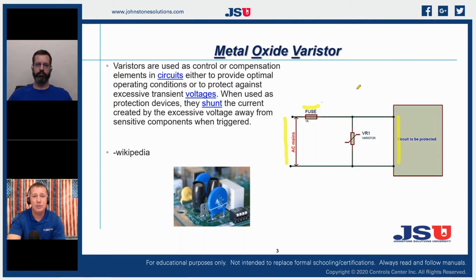And it doesn't use its resistance under normal operating conditions. What happens is when it sees a high amount of voltage, it generates heat and changes the resistance of the varistor so that it can redirect the current. So all it's doing is creating a new path of least resistance back to neutral or back to ground, depending on how the circuit is wired. Actually looking at this one, that says AC. That would have been a 120 system, so it would have had a hot and a neutral. So it was bringing it from hot to neutral, and it's going to land it back on neutral, or it's going to land it back on ground. If it lands it back on neutral, it's going to pop our breaker for us. If it lands it back on ground, it's just going to get it out of our path.